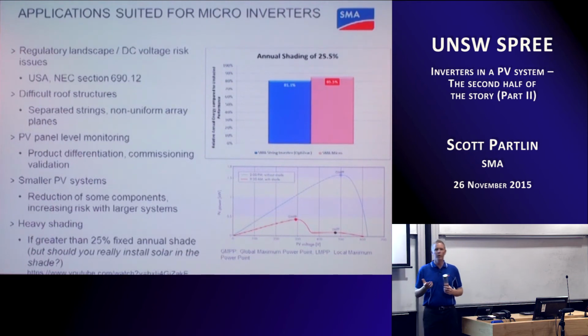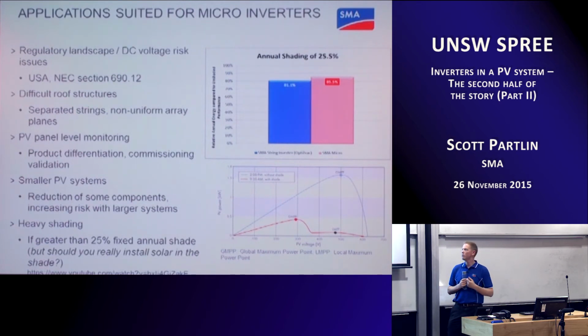So obviously we know that a solar panel works in the sunlight and it doesn't work in the shade. And so when they're shaded, they have a less than ideal operation. So in situations where you have very, very heavy shading, for example, if your PV array had more than 25% of it fixed shading throughout the year, a microinverter is going to offer a better energy output than an equivalent string inverter system. And that's just because they're able to do individual maximum power point tracking at the module level, as opposed to at the string level. But it's interesting to note that you can actually have quite a lot of shading in a system before the balance tips in favour of one technology or the other. Up to about that 25%, they can be reasonably equal.